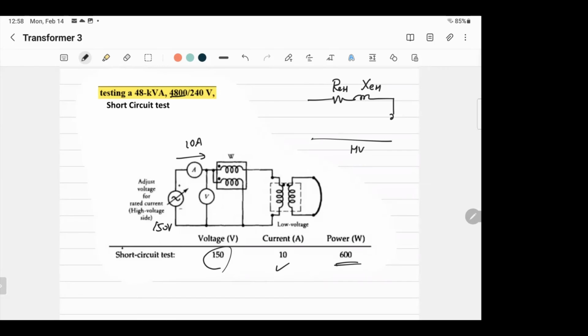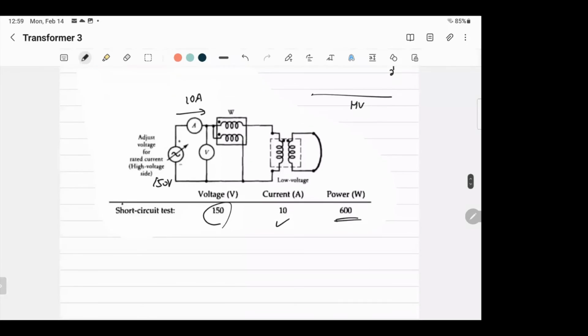The voltage measured is across the source and the rest of the circuit — across the whole transformer, so across the impedance. That's the magnitude. If you divide the voltage of the short circuit by the current of the short circuit, you get the equivalent impedance magnitude, since we're not considering angle yet.